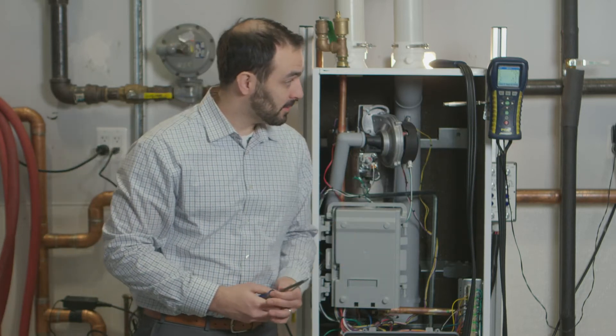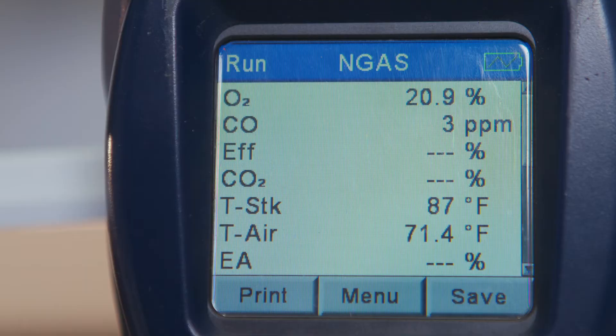I have my combustion analyzer up and running and sensing the room air. Right now it's reading 20.9%. If it doesn't say 20.8 or 20.9%, your analyzer is broken — don't use it. First thing we do, take off the vent cap and put in our probe.